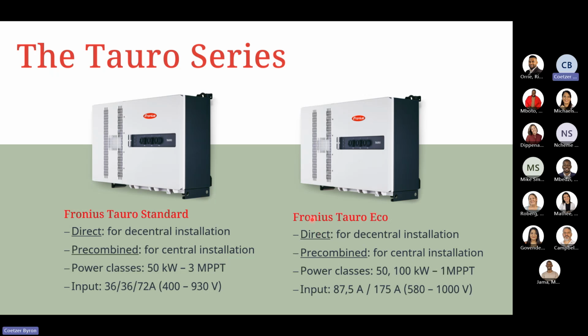Then we have the Fronius Tauro Eco. So the Eco is referring to a single MPPT power class unit. So it takes its name from the old Snap inverter Eco. It's exactly the same derivative and is also the same boards that are inside the unit effectively. So you've still got your single MPPT input. You've got your string fuses that are on the boards itself on the DC side. And again, it's available in power class 50 to 100 kilowatts. And then you've also got a voltage range that is very similar to the old Eco 27. So that's why we say it shares a lot of similarities between the two. So you've got 580 to 1000 on the input range. And again, your usable range would then be from 650 and above when using the Tauro Ecos.